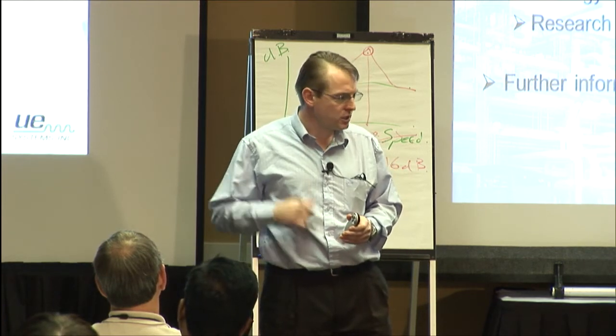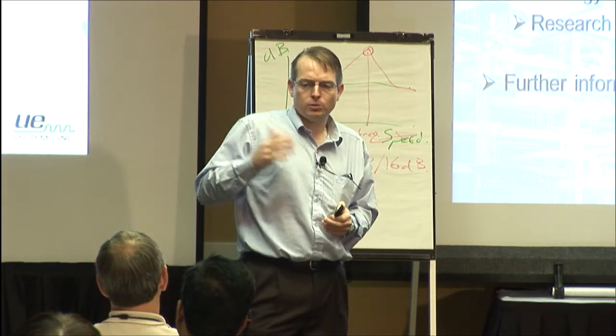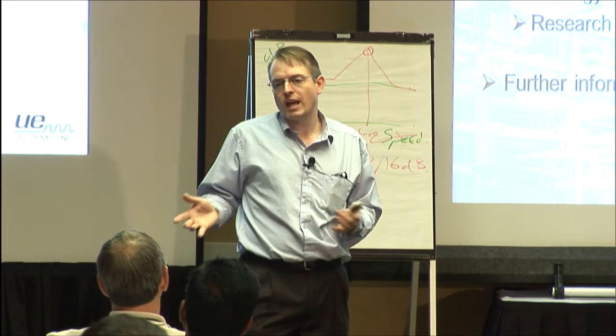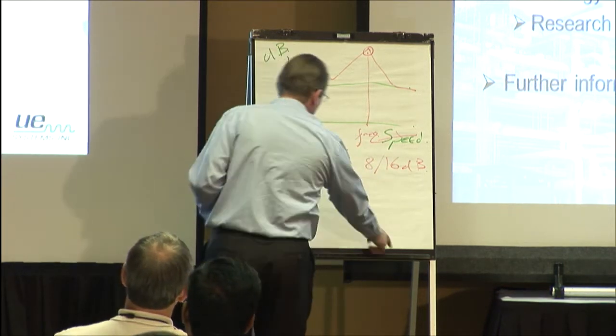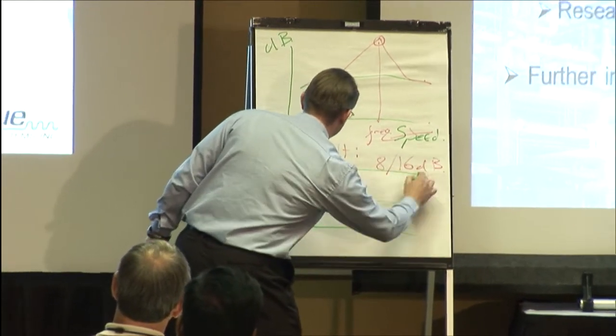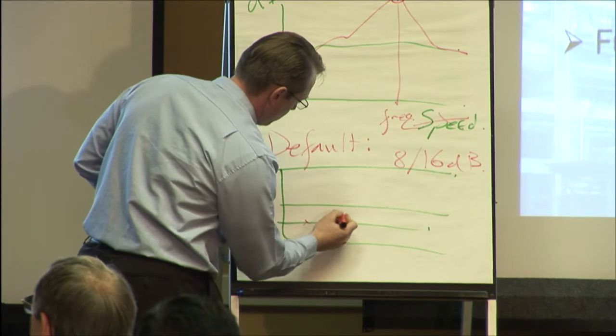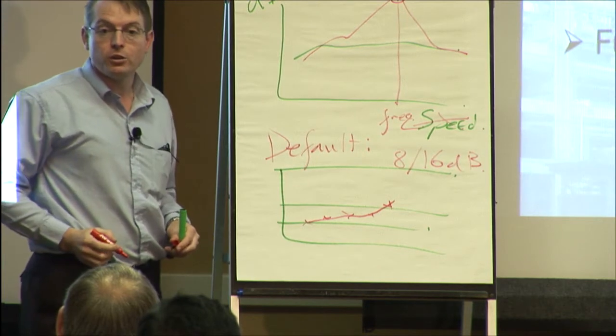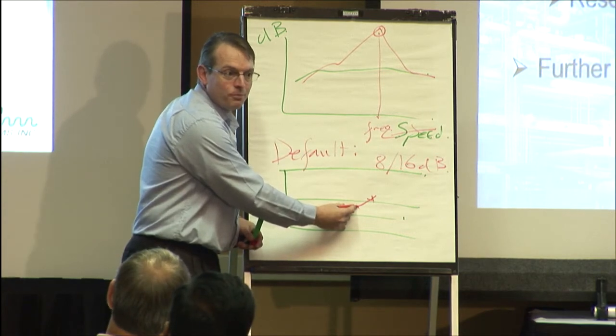The dB level is just a secondary thing in terms of a lubrication alarm, and this is where it comes back to. If you're prepared to accept you might have a few extra false positives, then you're just going back on a lube route, and you may not actually add any lube or maybe a tiny bit, because if you think about your standard dB trend for a bearing, there's your first alarm level, and then your baseline's here. This thing might trend along, and it's only once that gets through that alarm level you're going to go and lubricate it, right? It doesn't mean that you couldn't have gone and lubricated it here, and brought it back down.